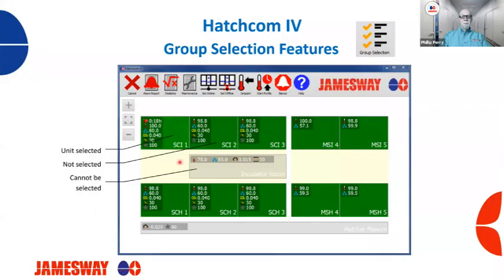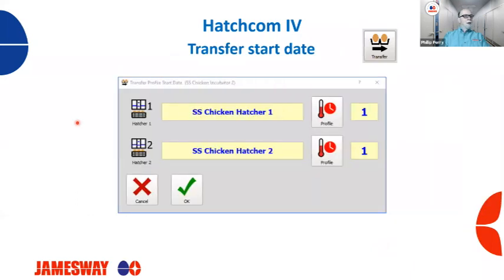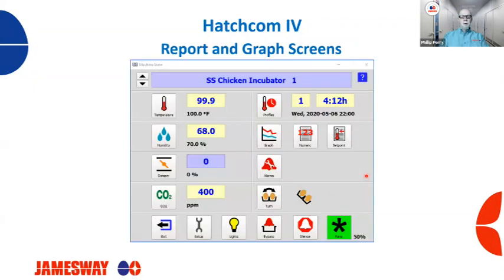So let's go back to the main screen here. We talked about the transfer and how to do the start date, and it's present on all incubators if the incubator is running a profile. So it allows you to change the start dates. I want to take a little time now to look at some of the new report and graph features. When you bring up a machine state, you'll see we now have the graph, the numeric report, and the set point report for this incubator all located right on the front of our machine state screen. It's useful now; we don't have to go up and open a file to get to each one. For the machine we want to look at, it's selected right here.